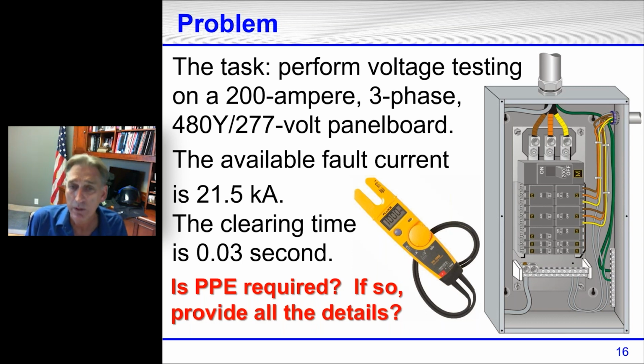You've got the panel board open. You're going to be doing voltage testing, so that means there are energized conductors and circuit parts. And if I were to ask everybody right now and show a hand or anything, everybody's going to say, yes, you have to wear arc rated or arc flash PPE. So let's look at this.